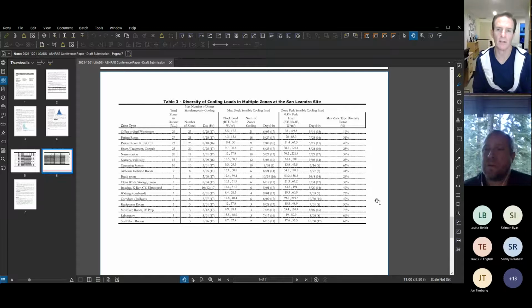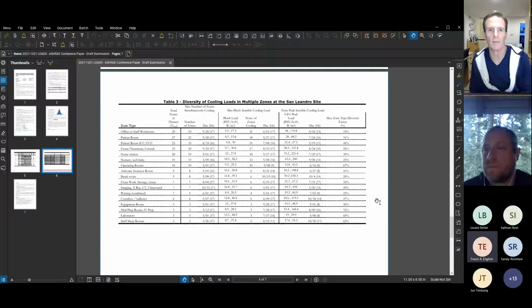But is it not true that there is reheat happening even in those cooling hours? Yeah. This is called a cooling hour if the room set point is 72 and the supply air temperature is 70 or 71. That's considered a call for cooling because it takes at least 1 degree of cooling in this data. But to your point, the supply air coming off the air handler is probably 55 and we're doing 18 degrees of reheat at that point, but we're still calling that a cooling load.